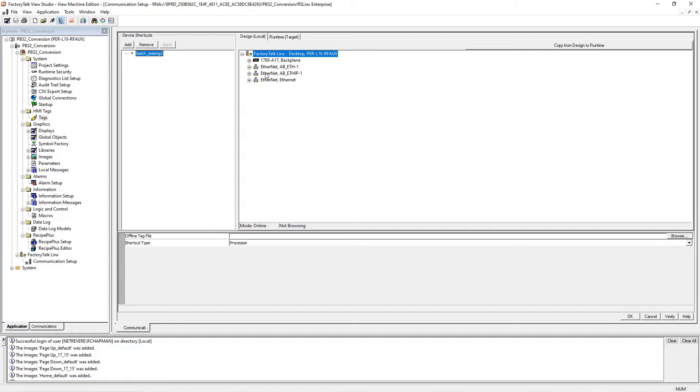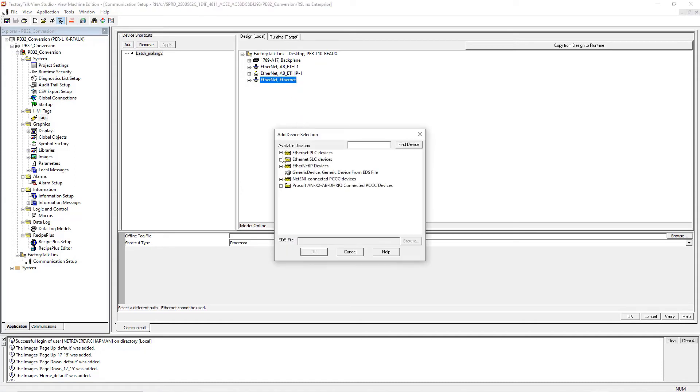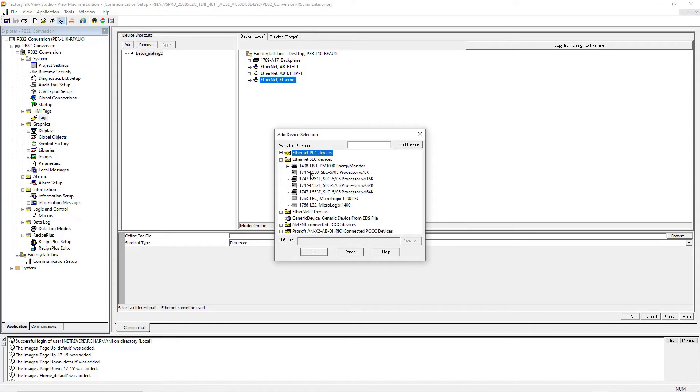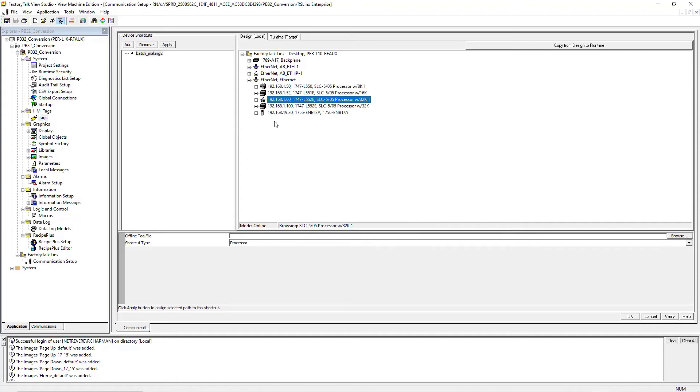And then we want to definitely use Ethernet, don't use these other two. Right click, add device, and we're going to set it up for SLC-5/05. Give it the IP, say OK. Make sure the correct PLC is highlighted, and then click Apply. If you don't get this confirmation window, then it didn't work. Hit Yes on here.